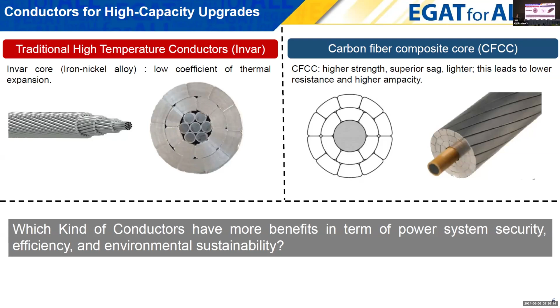When upgrading the transmission line with a high temperature, low sag conductor, several options exist. But for the traditional Invar conductor, with a low coefficient of thermal expansion, EGAT has been utilizing this kind of conductor for a long time. But the primary issue is a higher transmission line loss than the ACSR conductor due to higher resistance. Another one is the carbon fiber composite core, or CFCC, which has better strength, lower sag, and less weight, resulting in reduced resistance and increased capacity. But EGAT has not utilized this type of conductor before. So, which kind of conductor has more benefit in terms of power system security, efficiency, and environmental sustainability?